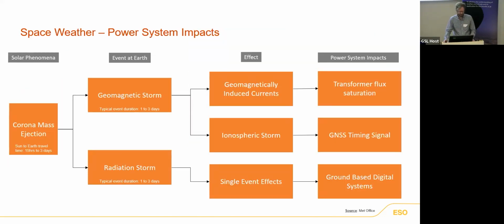This slide highlights the areas of solar weather we'd be concerned about from the ESO's point of view, and how that leads to risks on the transmission system. Starting from the left, we've got coronal mass ejections, the solar phenomena that leads to geomagnetic storms at Earth, which leads to geomagnetically induced currents in the Earth and in the transmission system, and then to saturation of transformers on our network. That's probably where the biggest risk to the network lies.